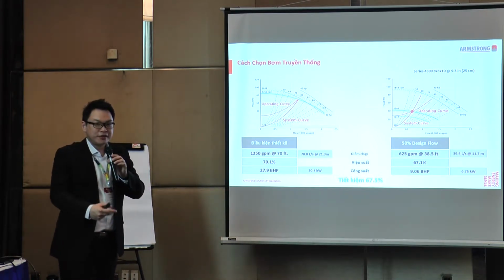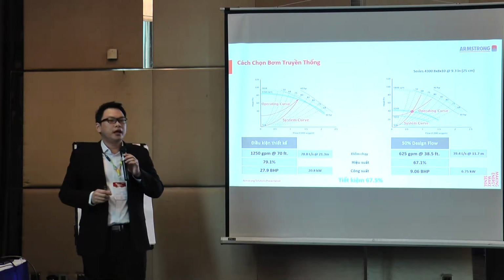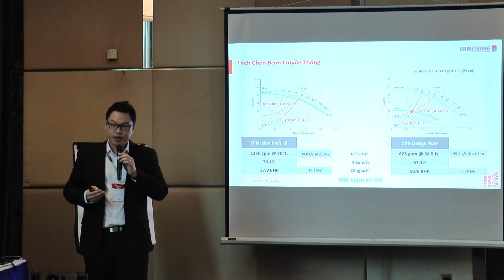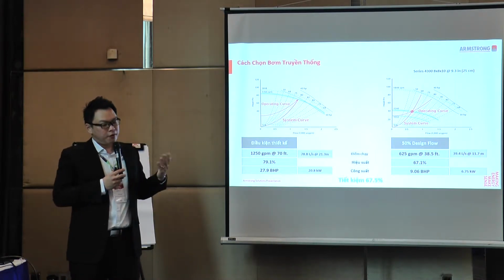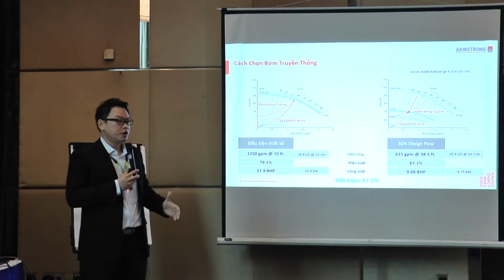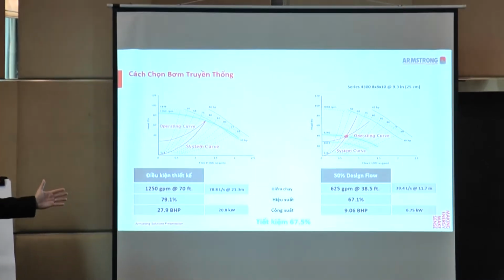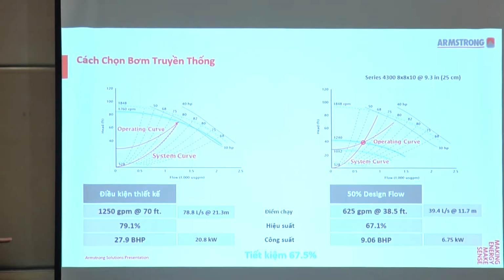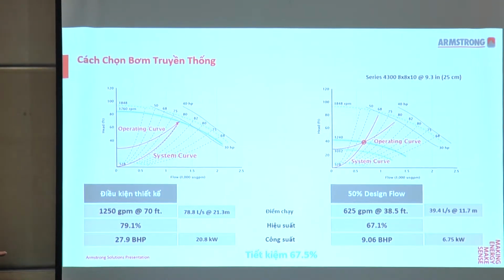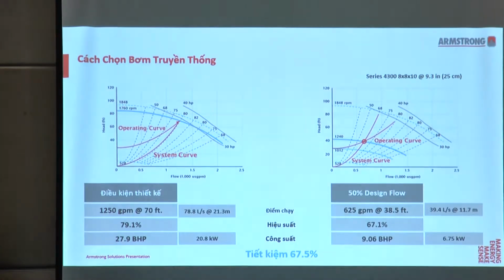If you do the math, it is about 67.5% energy savings. If you're familiar with the ASHRAE standard 90.1, it states that at 50% flow, it has to have 70% energy savings. Since this is 67.5%, it does not meet the requirement, because it's below 70%.